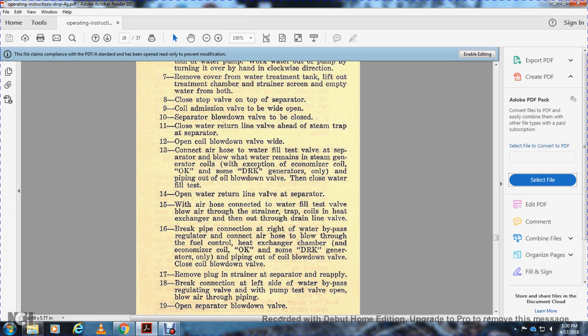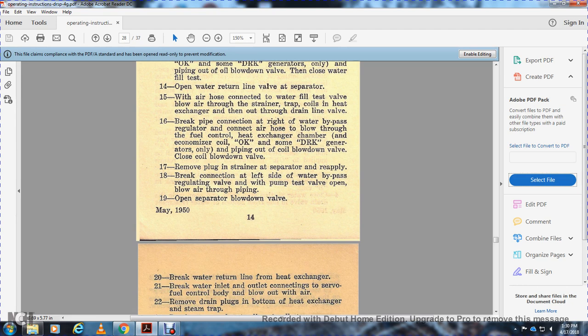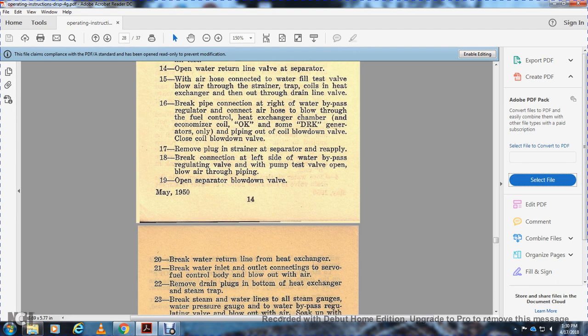18, break the connection with the left side of the water bypass regulating valve with the pump test valve open, blow the air through the piping. 19, open the separator blow down valve. 20, break the water return line from the heat exchanger. 21, break the water inlet and outlet connection to the servo fuel control body, blow out with the air. 22, remove the drain plug from the bottom of the heat exchanger and the steam trap.